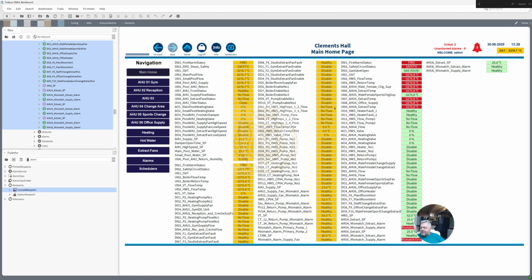And I'm bringing in all the points at the moment because I've got to work on these points. So every one has got a history attached to it, apart from some of the alarms. I'd rather bring all the points in, work on all the points, and then take the points and put them to the pages, and take the critical alarms like the safety circuit and the fire alarm and the gas valve. These 3 will definitely end up down at the bottom.